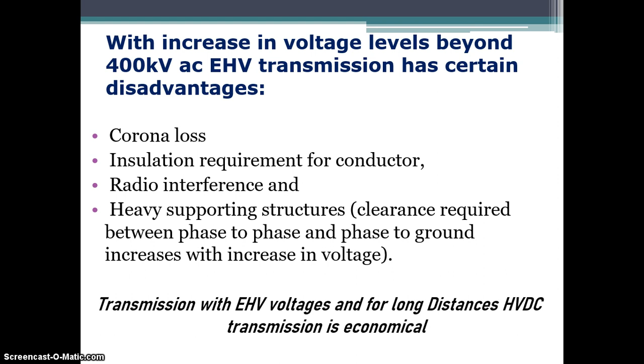So here if the distance increases beyond a certain value, then HVDC systems are most economical. So the value is 600 kilometers approximately, and these are the advantages for HVDC transmission: first, there is no skin effect. Second, lower transmission losses. Then we have voltage regulation which is better in an HVDC line. Extra high voltage AC lines are loaded less than 80% of the normal load. So this is one of the important factors, that extra high voltage AC lines are loaded up to only 80% of their normal load. So voltage regulation will be better in HVDC, low corona and thus less radio interference.